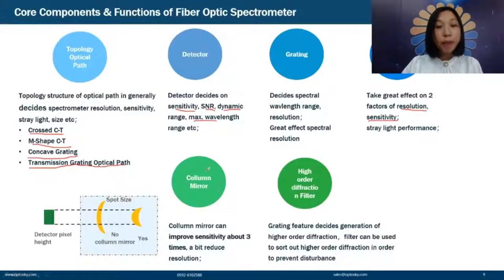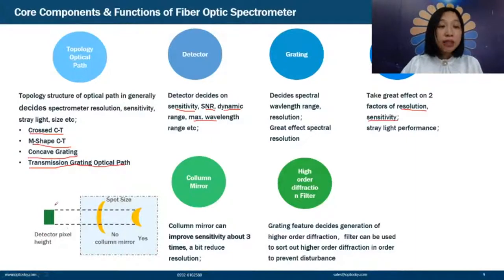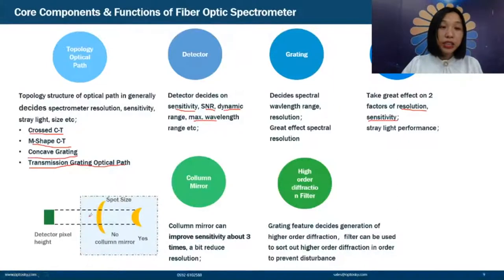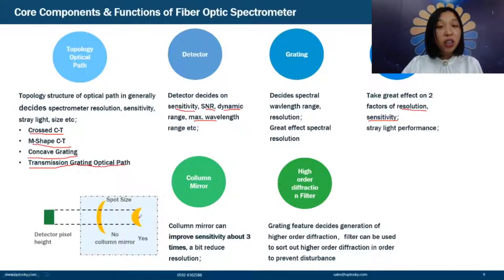Fifth is the cylindrical mirror, which can improve sensitivity by about three times. The detector height is only about 200 micrometers, and the spot beam from the grating is shaped like a crescent moon — thin and long — so most energy is not absorbed. By adding a cylindrical mirror, we can compress this crescent shape to be fatter and shorter, allowing 80–90% of light energy to be absorbed by the detector.